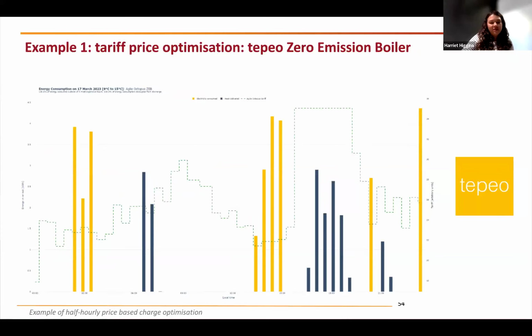This is an example of flexibility use cases, looking at one day of one of our zero emission boilers, or ZEBs. For those not familiar, ZEBs charge up a thermal storage core using resistive electric elements, storing up to 40 kilowatt hours of heat, which is released to the property via the existing wet central heating system when the thermostat calls for heat. In this graph, the yellow bars show the ZEB charging and the blue bars show it discharging heat to the property, with the dotted line showing one day of the Octopus Agile tariff, an existing market tariff, to demonstrate how much flexibility you can get from thermal storage.